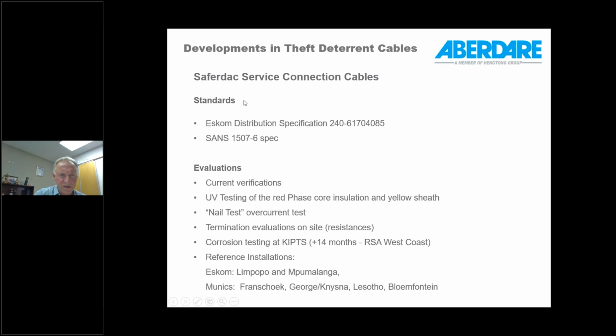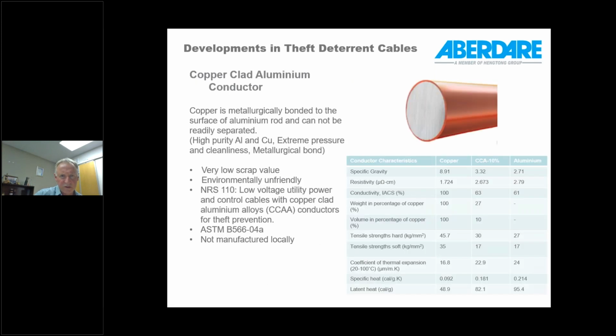The standards that are applicable are the Eskom distribution specification listed here, and also the SANS 1507 Part 6 specification, which had been amended. A number of evaluations had been done for current verification, UV testing, a nail test to test for short circuit overcurrent capability and burning of wires, creating an open circuit. Termination evaluations for resistance were done on site at the Eskom site. Corrosion testing was done, and there are now a number of reference installations for these kind of cables. So quite widespread at this stage.